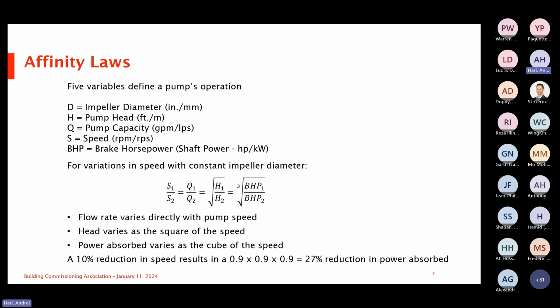And I stop at this slide because there's a lot of information. And if you remember the affinity laws, everything that we're going to talk about builds on the next 2 slides. Now, first of all, the affinity laws tell us that there are 5 variables that define a pump's operation, those being the impeller diameter, the head, the flow, the speed, and the brake horsepower. Now, what ASHRAE is saying is that when we reduce the flow, we should drop the energy by 70% at 50%. Well, that's just following the affinity laws.